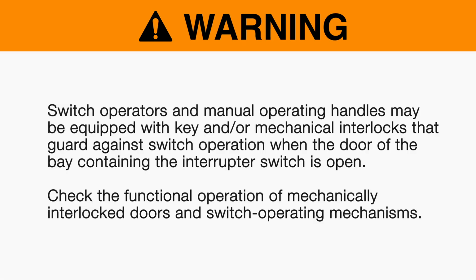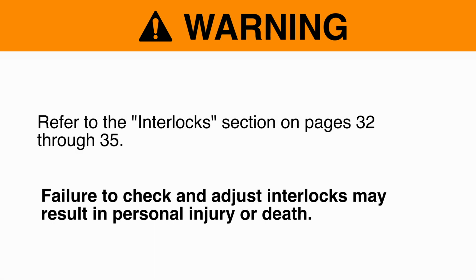Warning: switch operators and manual operating handles may be equipped with key and/or mechanical interlocks that guard against switch operation when the door of the bay containing the interrupter switch is open. Check the functional operation of mechanically interlocked doors and switch operating mechanisms. Refer to the Interlocks section on pages 32 through 35 of the written instructions. Failure to check and adjust interlocks may result in personal injury or death.